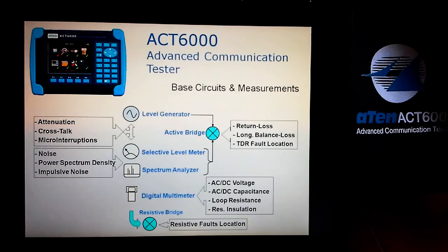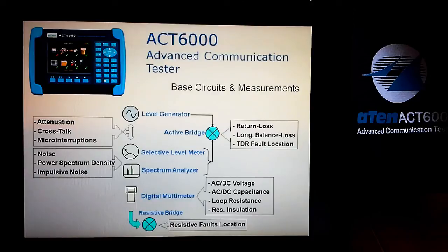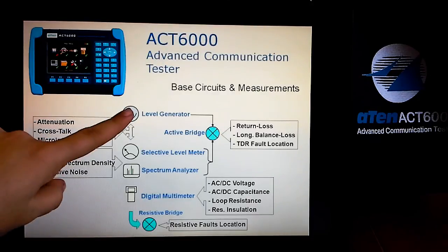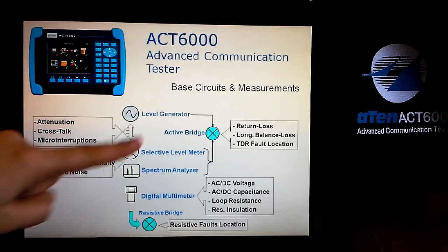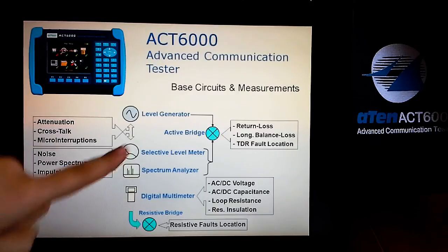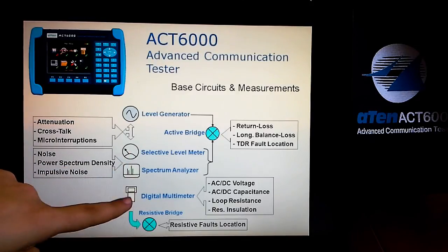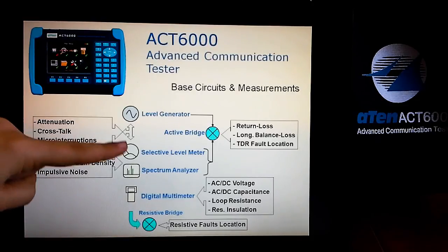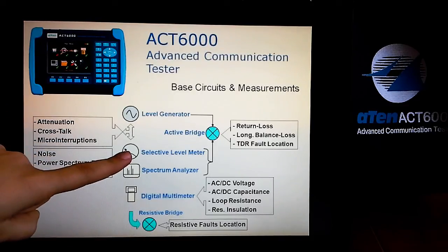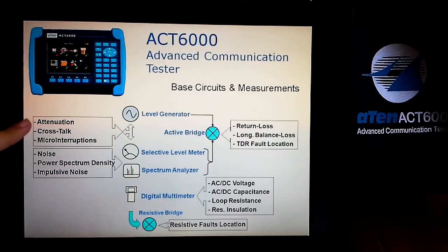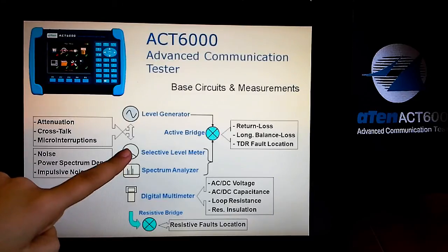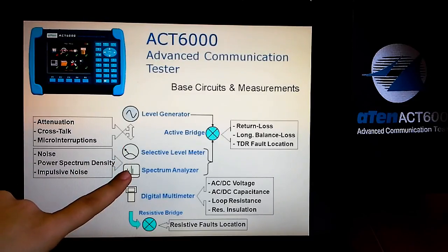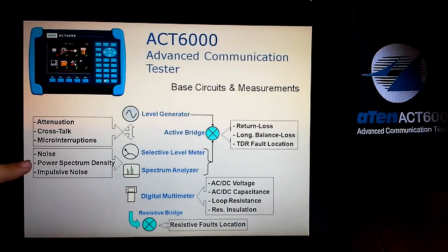The base circuits of ACT6000 are: level generator, active bridge, selective level meter, spectrum analyzer, digital multimeter, and resistive bridge. From the level generator and selective level meter, you can check attenuation, crosstalk, and micro interruptions. From the selective level meter and spectrum analyzer, you can check noise, power spectrum density, and impulsive noise.